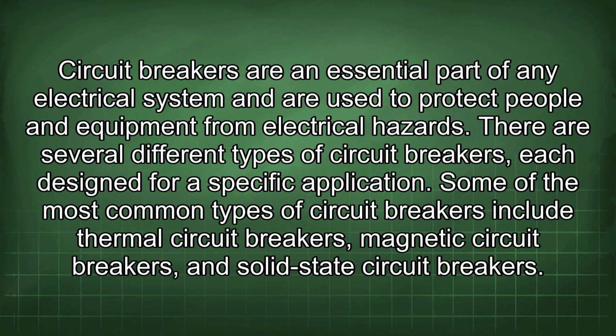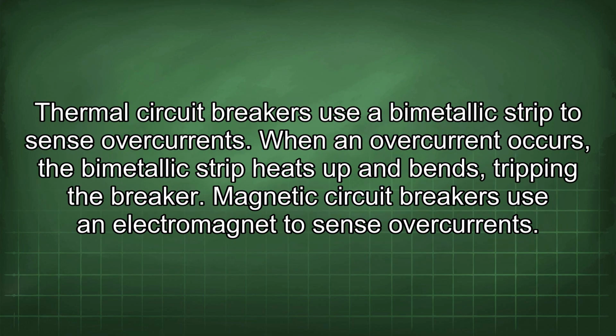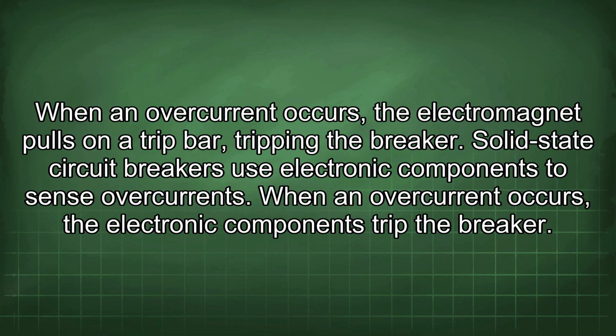Circuit breakers are an essential part of any electrical system and are used to protect people and equipment from electrical hazards. There are several different types of circuit breakers, each designed for a specific application. Some of the most common types include thermal circuit breakers, magnetic circuit breakers, and solid-state circuit breakers. Thermal circuit breakers use a bimetallic strip to sense overcurrents. When an overcurrent occurs, the bimetallic strip heats up and bends, tripping the breaker. Magnetic circuit breakers use an electromagnet to sense overcurrents. When an overcurrent occurs, the electromagnet pulls on a trip bar, tripping the breaker. Solid-state circuit breakers use electronic components to sense overcurrents. When an overcurrent occurs, the electronic components trip the breaker.